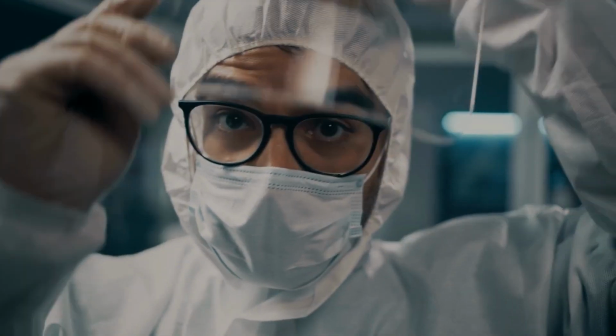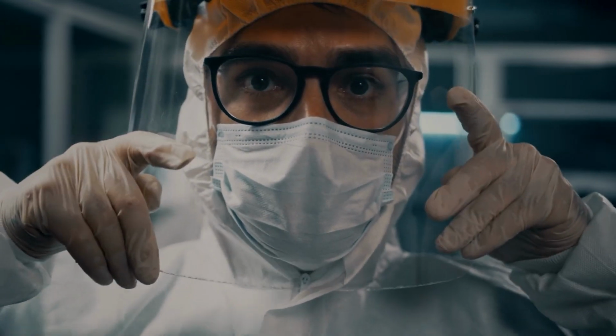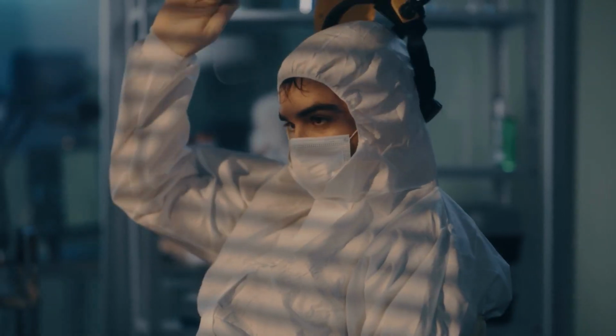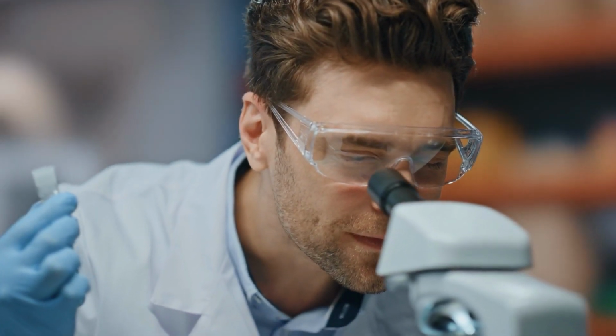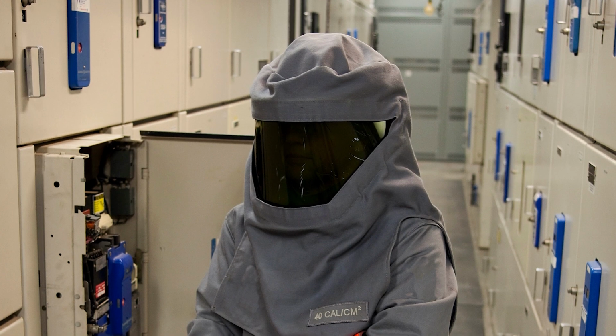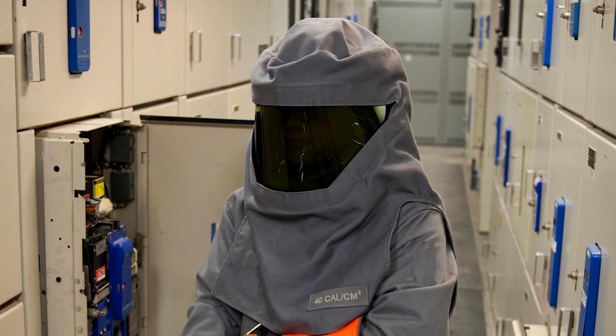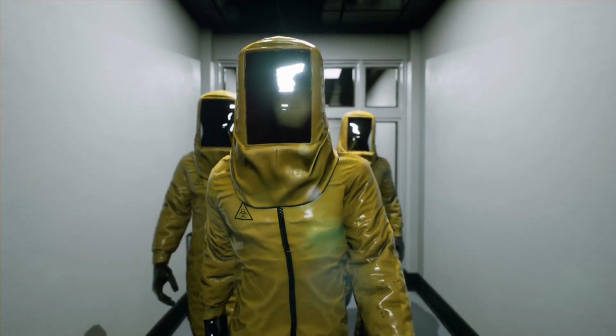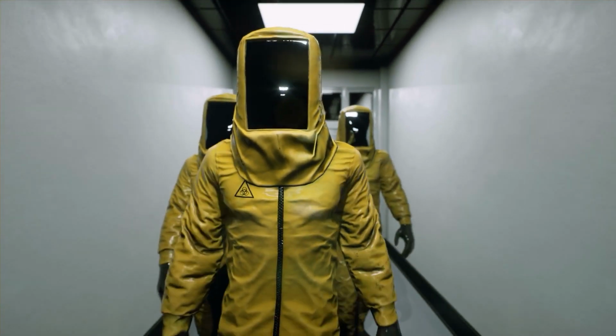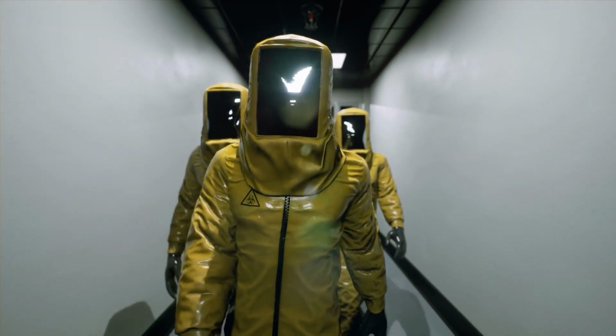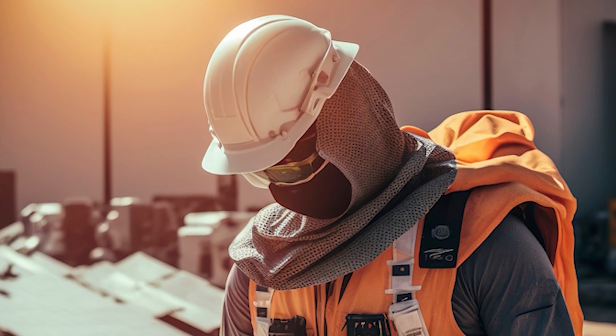electrical work. Employers should always select face shields that are rated for arc flash protection according to industry standards such as ASTM or ANSI. Specifically, non-conductive safety glasses protect the eyes from electrical hazards, flying particles, and chemical splashes. Just like face shields, employers should also select safety glasses with non-conductive frames and lenses that meet ANSI Z87.1 standards for impact resistance. The arc-rated hoods protect the head, neck, and shoulders from high temperatures and electrical arcs. Similarly, employers should select hoods with an arc rating that matches or exceeds the expected level of electrical exposure, as specified by standards such as NFPA 70E.